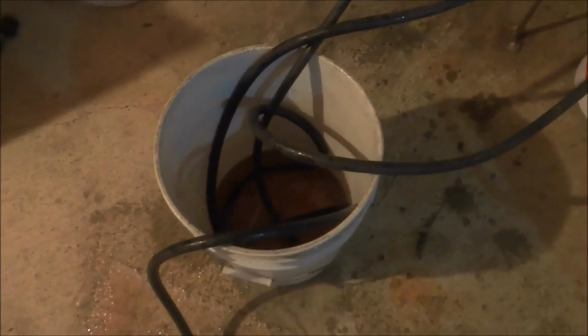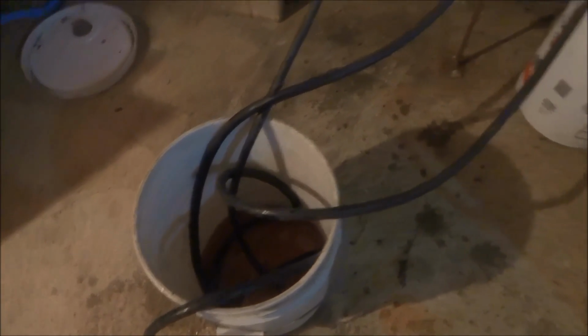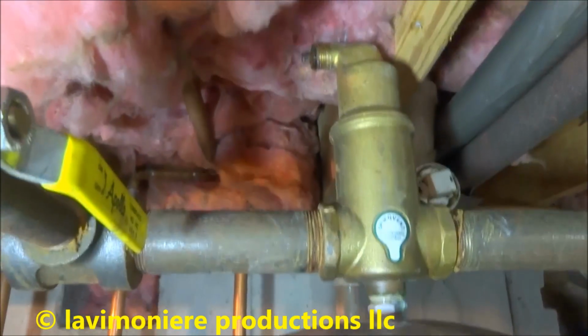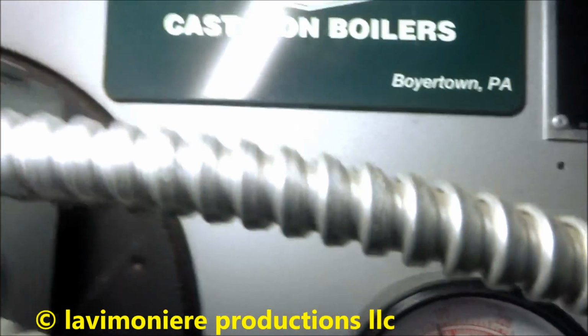We'll check that, we'll see what that is. Alright, the leak valve in it below, so that's good. Got them two valves, all them valves opened. This is not leaking. Our pressure's good at about 18. And it's coming up to speed.